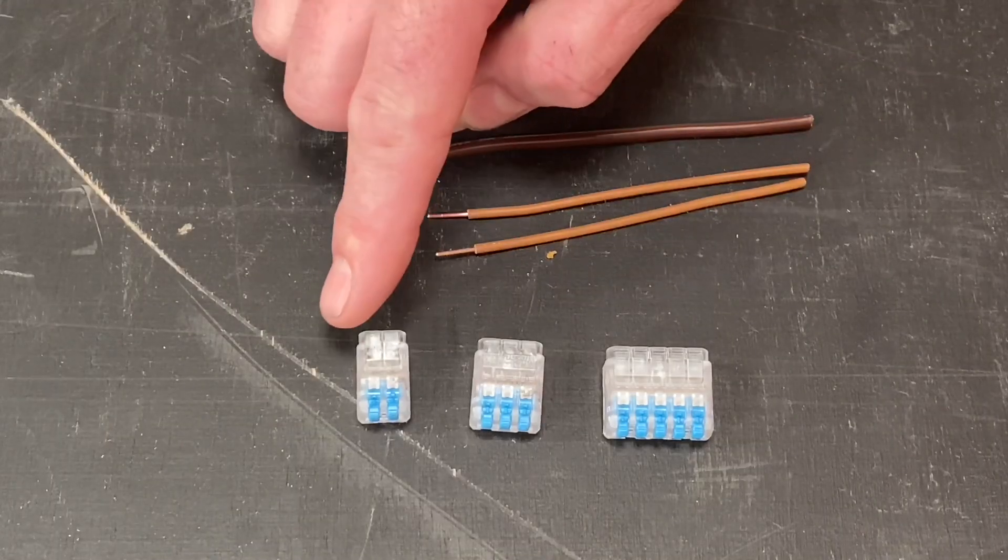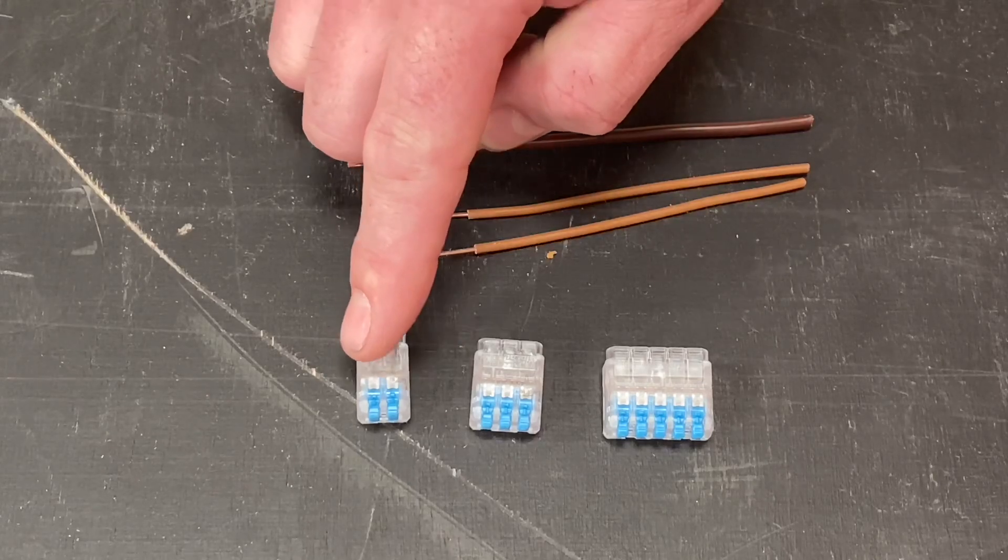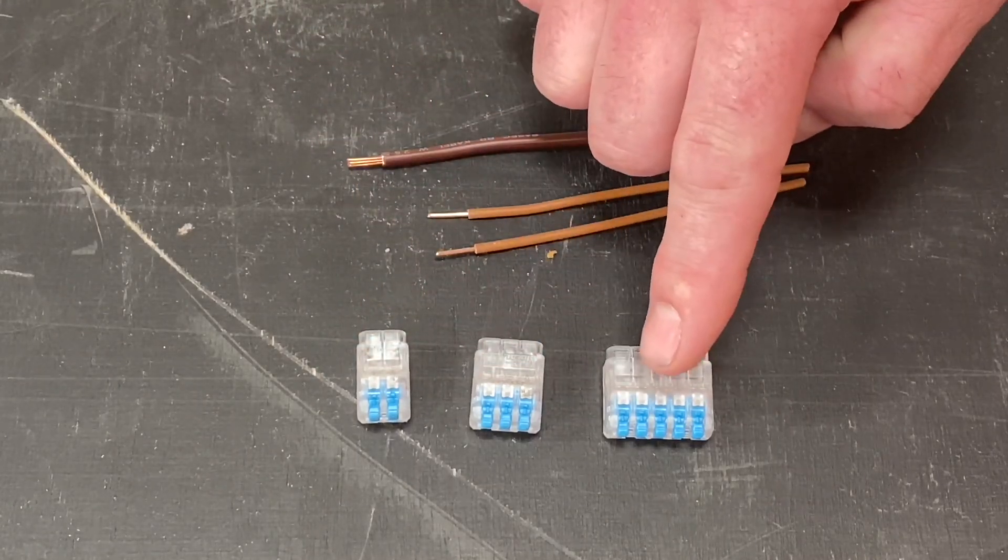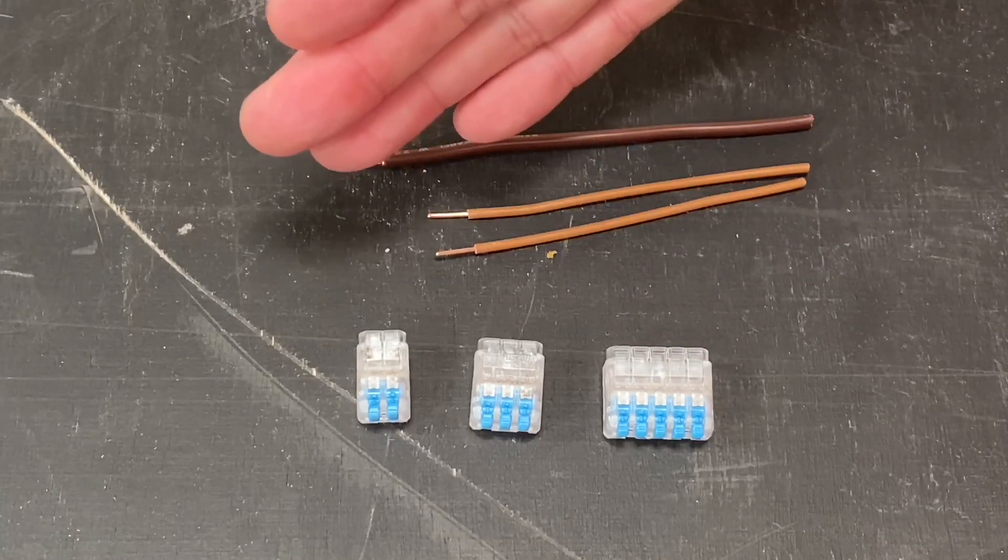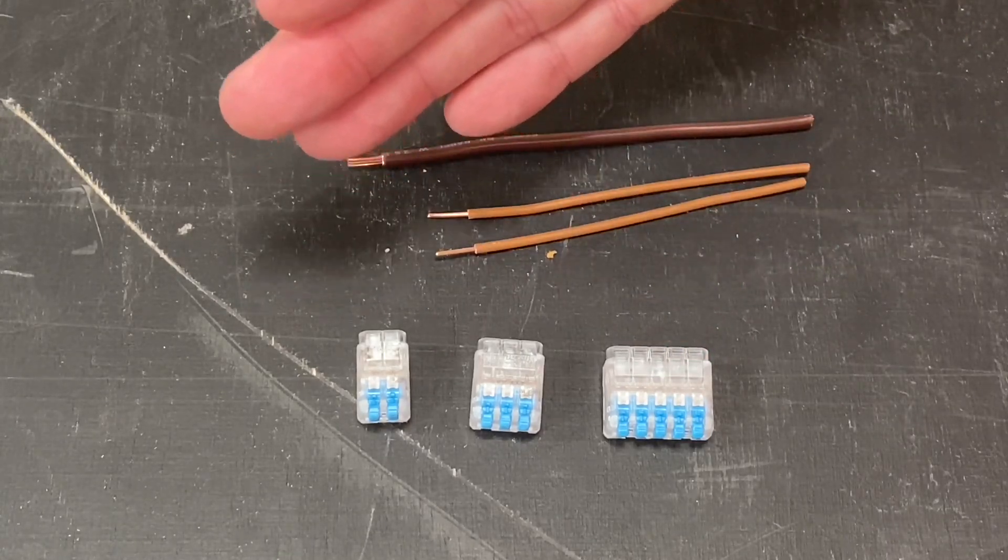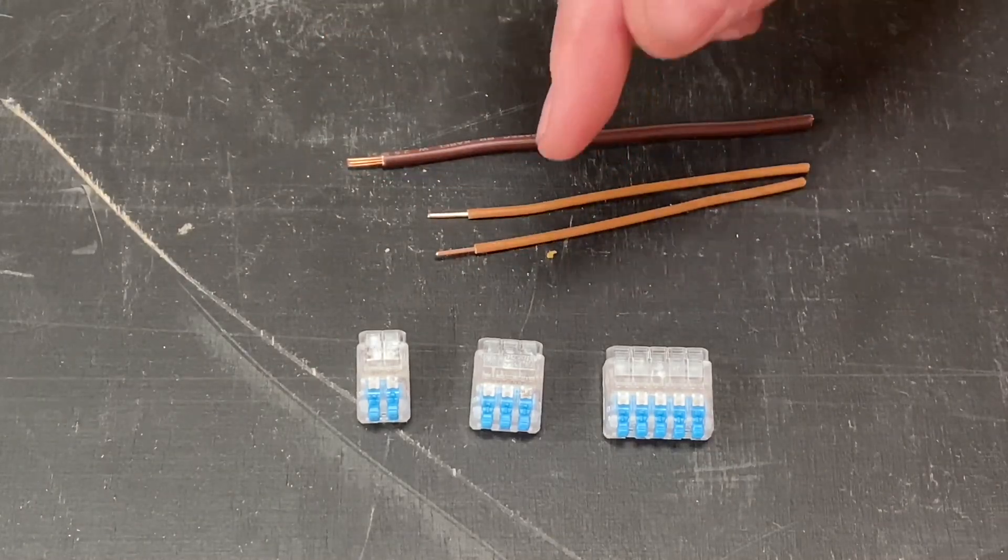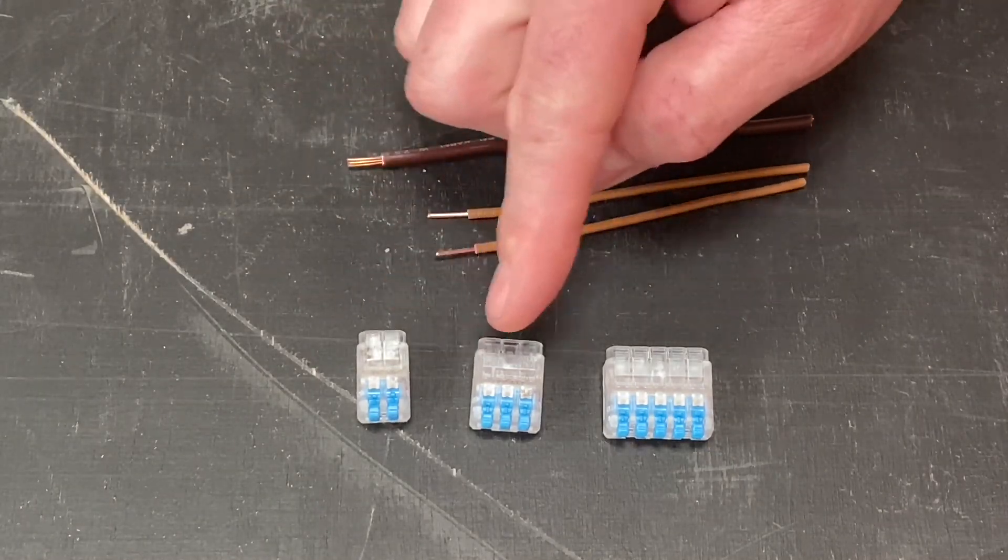Let's start with the lever variety of the In-Sure connectors. We've got a two conductor connector, a three conductor connector, and a five conductor connector. They go from 0.2 millimeters squared up to 2.5 millimeters squared cables and cover fine stranded, stranded, and solid copper, and they're rated at 24 amps each.